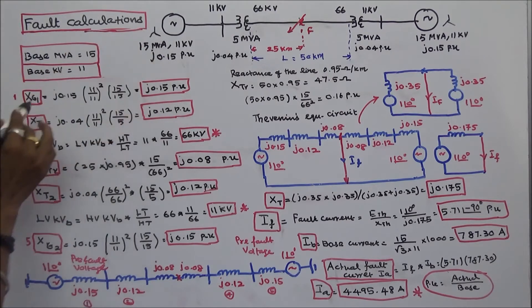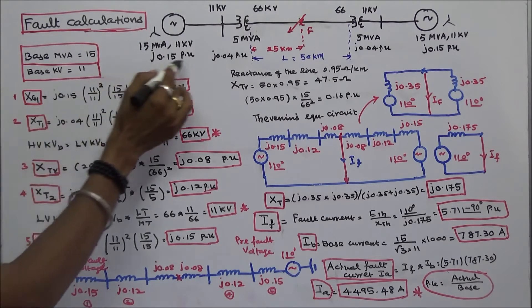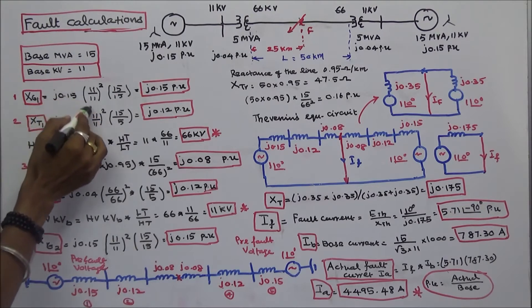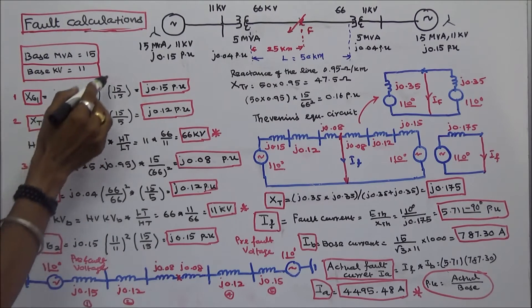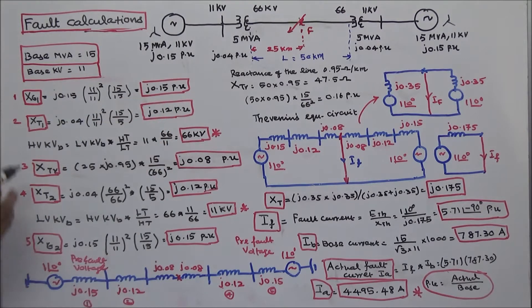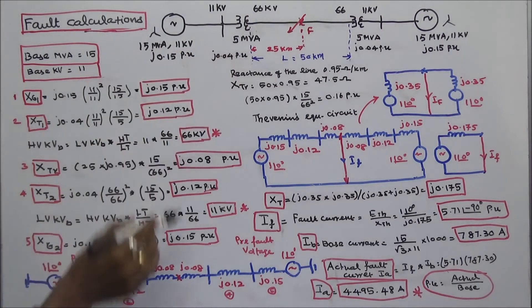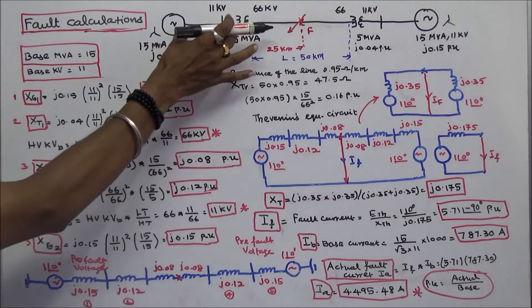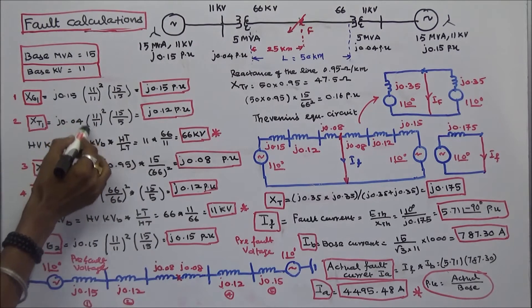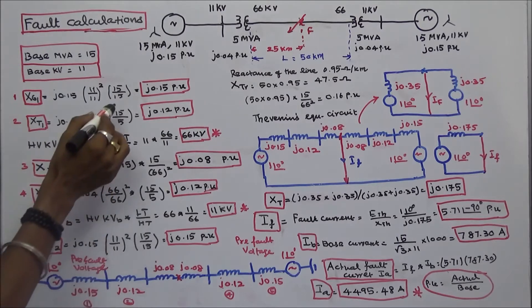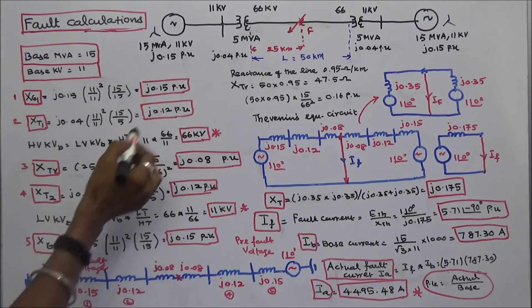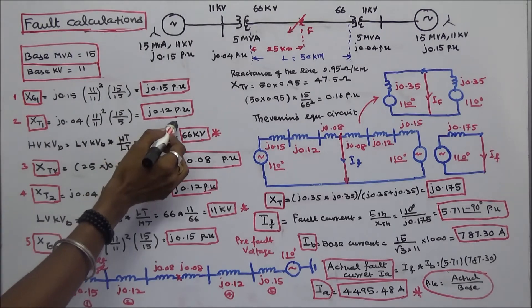For Generator 1, the given reactance value is J.15. Applying (11/11)² × (15/15), that is equal to J.15 per unit. For Transformer 1, the given value is J.04 × (11/11)² × (15/5), that is equal to J.12 per unit.